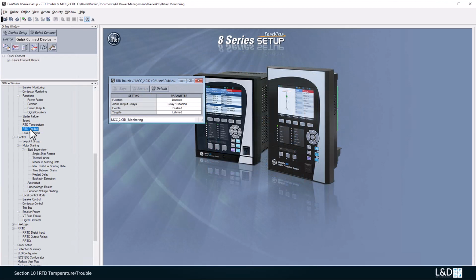When set to alarm or latched alarm, the RTD trouble element monitors all the RTDs that are programmed as alarm, trip, or configurable, and generates an alarm if any of the RTDs are detected as open or shorted. Upon detection of an RTD open or shorted condition, the element also asserts the RTD trouble PKP and RTD trouble OP and operates the assigned output relay. Both RTD and RRTD can be monitored using this element.